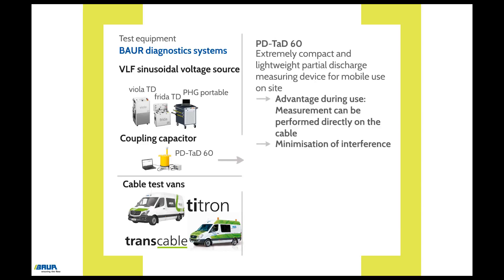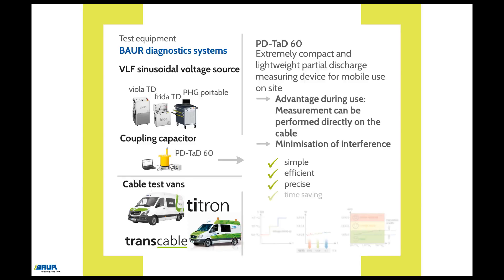The PD-TaD 60 represents the most compact and lightweight partial discharge measuring device for mobile use on site. This portability makes it possible to perform the measurement directly on the cable, which minimizes interference and thus represents an important precondition for precise and meaningful measurement results. Checking cable routes with the PD-TaD 60 is simple, efficient, and precise. It also saves time because the dissipation factor measurement and partial discharge testing are performed in parallel. A comprehensive checking of newly laid or repaired cables, as well as general condition evaluation, can therefore be performed quickly and simply in a single operation, without significant extra expense.